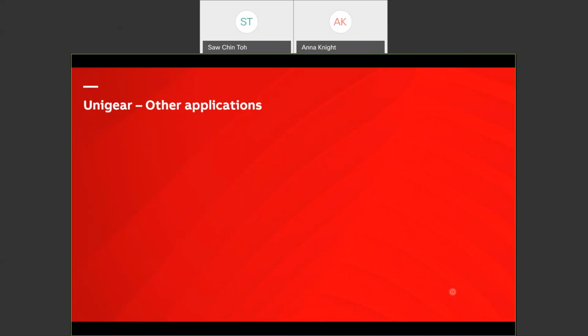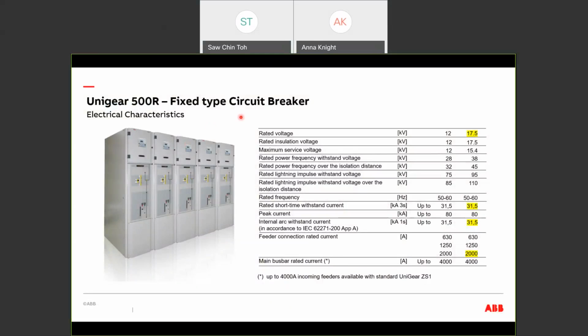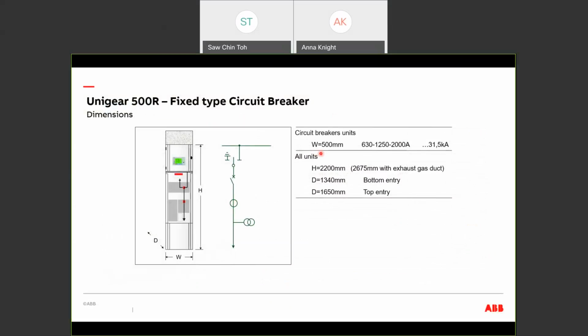UniGear is a very big family of ABB air insulated switchgear. It not only offers withdrawable switchgear, but also other functions as well. For example, the UniGear 500R is an air insulated switchgear panel with fixed type circuit breakers. The maximum rating of the UniGear 500R is 17.5 kV, 2000 amps, and 31.5 kA. Regardless of configuration or rated current, we have only one standard width, which is 500 millimeters. It is very compact. The depth of the cubicle is 1.3 meters for bottom entry and 1.6 meters for top cable entry. The panel consists of a 3-position switch, the breaker, as well as the CTs and VTs.